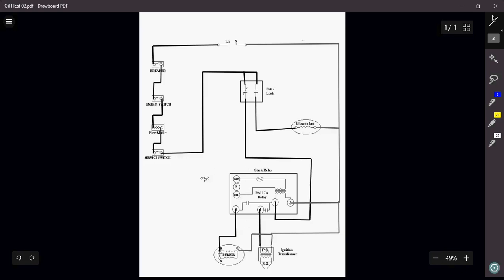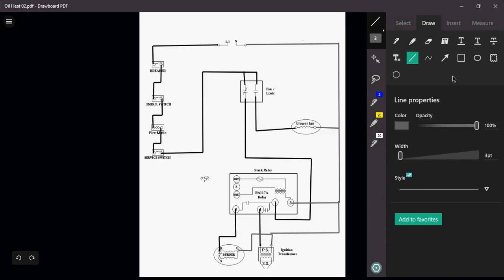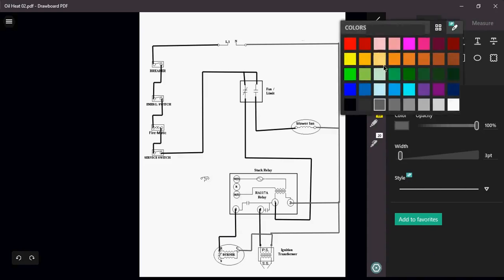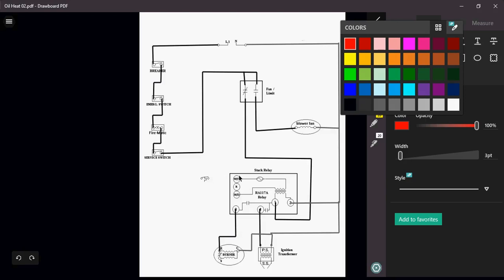Okay, so the last thing that we have is the thermostat. So I got W, R, and B. Now remember, W, R, and B, I'm going to use all three of these if I was actually using maybe like an aquastat or something like that. But since I'm using just a thermostat that's going to be up in the space, I'm going to be using W and B, or better known as T, T.